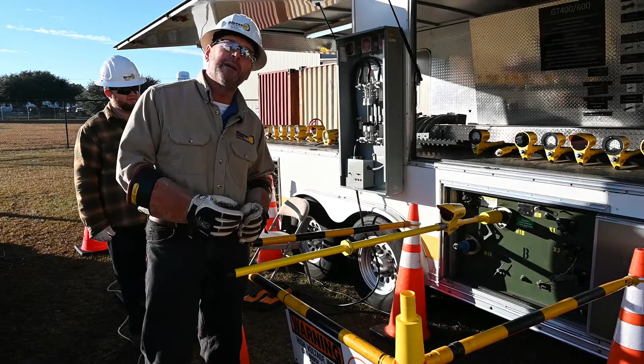So now the tool tells us we're de-energized. The tool is accurate enough, and we're confident it's telling us we have a lack of system voltage, we don't have induction, and we have an absence of any backfeed. But how do you know the tool was functioning properly and was accurate? So now what we're going to do is test the tester.